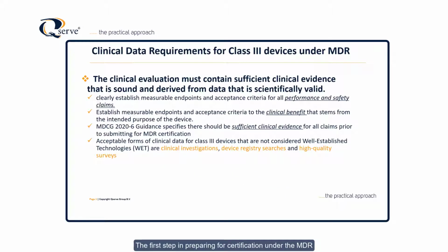The first step in preparing for certification under the MDR is to take a look at your clinical evaluation that was certified under the MDD. MDCG 2020-6 guidance specifically states that there should be no clinical data gaps in MDR applications. PMCF should have been done under the MDD.